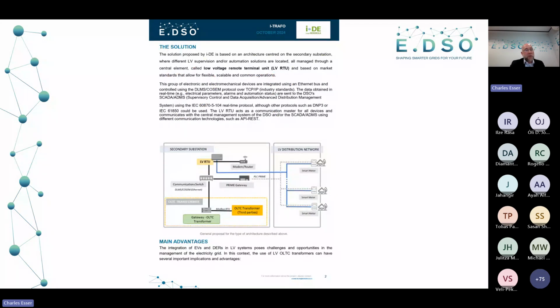The solution brought up by our member i-DE is based on an architecture centered on the secondary substation, where different low voltage supervision or automation solutions are located, all managed through a central element called the low voltage remote terminal unit, based on market standards. You can see there a proposal of the type of architecture that's based on this.